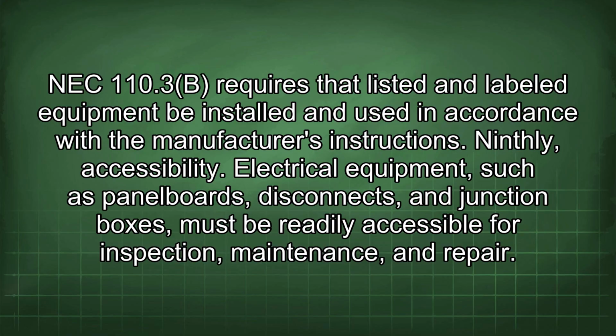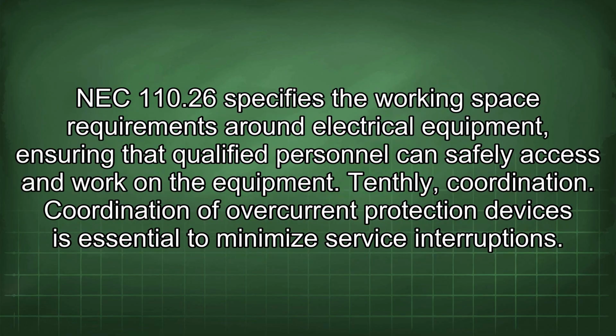Ninthly, accessibility. Electrical equipment such as panel boards, disconnects, and junction boxes must be readily accessible for inspection, maintenance, and repair. NEC 110.26 specifies the working space requirements around electrical equipment, ensuring that qualified personnel can safely access and work on the equipment.